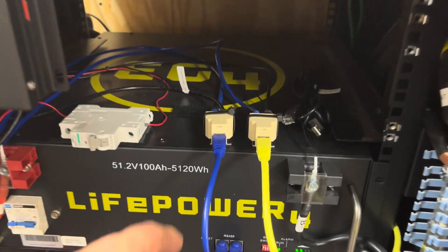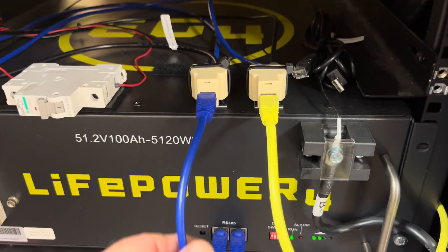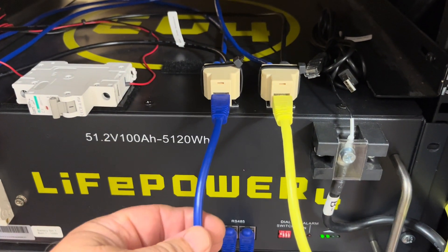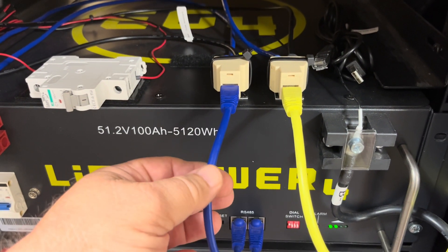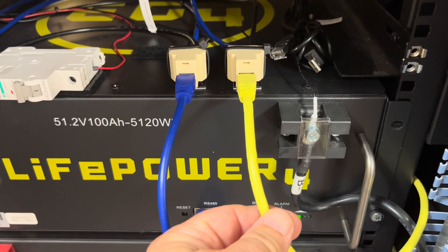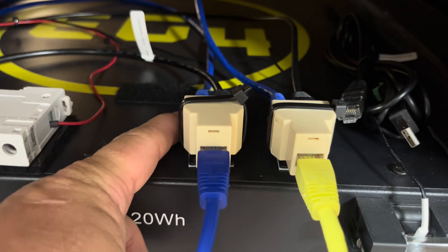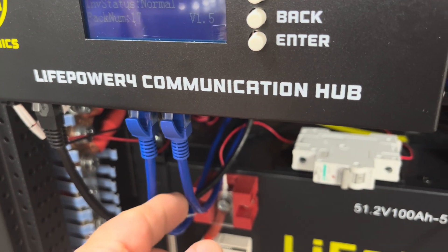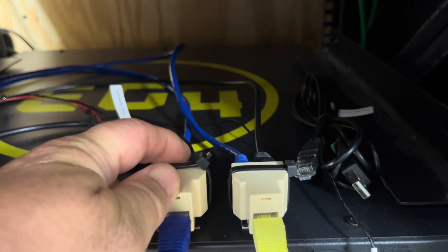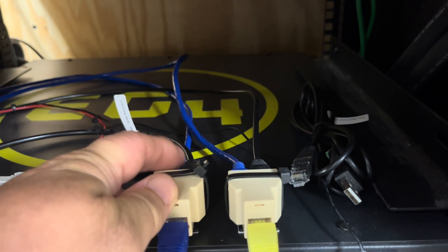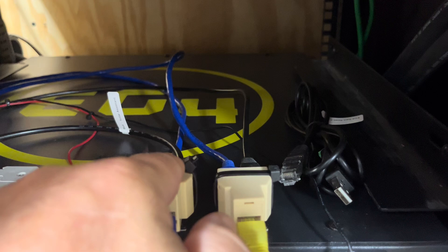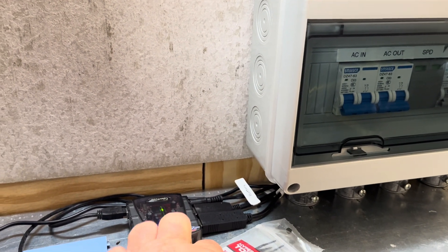These go back over to the battery banks on these splitters. This is my port one which is 15 batteries and my port two which is two batteries. They're connected via the splitter. One cable runs to the LifePower4 communication hub from both of them, and the other cable is an RS485 to USB adapter cable connecting in the back and running over here to this communication hub.